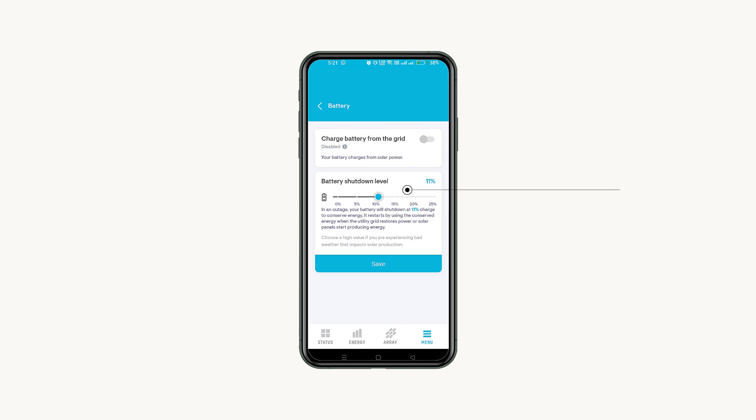You can also set up your battery shutdown level percentage. During a power outage, it will shut down your batteries when they reach a set charge percentage to conserve some energy which will help them to restart when the utility grid restores power or solar panels start producing energy.